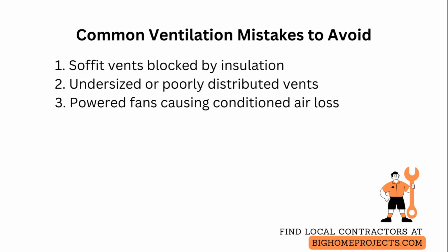A third problem is installing powered attic fans without accounting for air leakage from the living space, which can pull conditioned air into the attic and raise energy use. Avoid this by sealing ceiling penetrations and using fans only when justified, not as a substitute for proper passive ventilation.